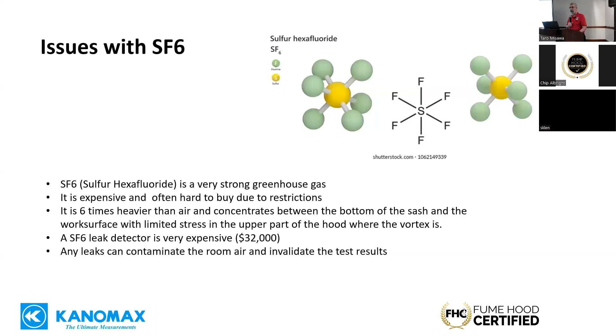So that is another problem. So just to give you an example of bad practices that happen, I've seen testers come in and have a leak, and they get SF6 in the room, so the background goes up, so they're showing failing before they ever expose the probe to the hood. And so what I have seen done is that they will recalibrate using contaminated background. So if the background is 10 parts per million and they calibrate that to 0, the hood's got to leak a huge amount to show up. So, you have to have a certain trust in your testers that they're doing it correctly.